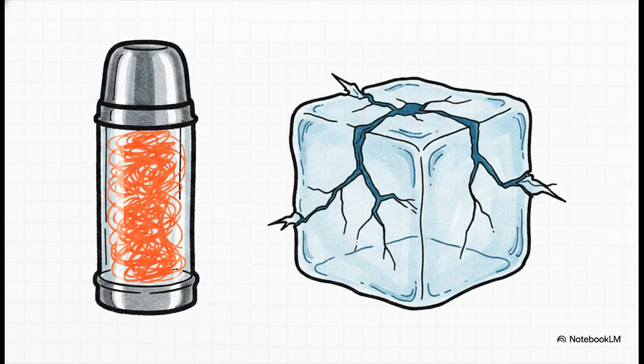I like to think of it this way. Oil is kind of like a thermos. It's completely sealed, hiding all this quiet work inside. But if something goes sideways, the failure can be violently explosive. Luckily, the oil actually gives us an early warning through dissolved gas analysis way before things go boom. Resin, though? Resin is like an ice block. You can see right through to the coils, but the failures are silent. If extreme humidity or thermal cycling causes that hidden damage to crack the resin, well, it cracks fast, and by then, it's totally game over.